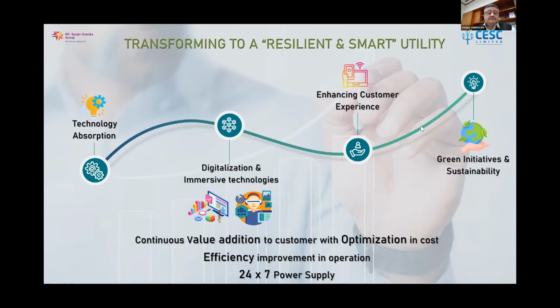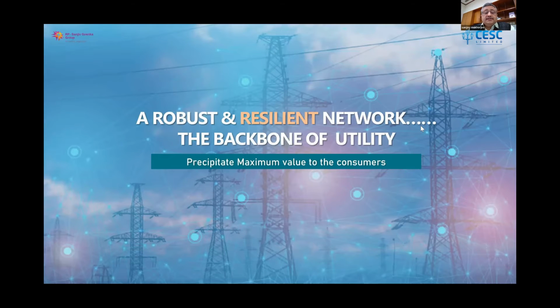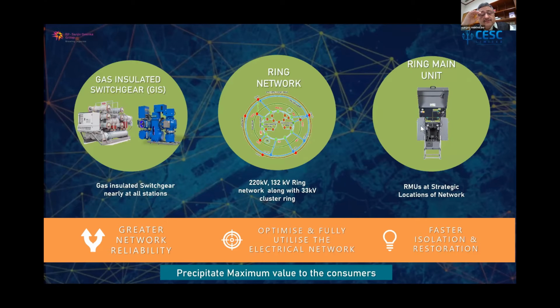Now, going ahead, if we talk about a robust and resilient network, which is the very backbone of any utility, we start from the 220 kV level, because we are one of the only discoms in the country having 220 kV as its distribution network. We have our own network starting from 220 kV going down to 220 volts. We have been using gas insulated switchgears since the mid-90s, and almost all stations use them now, shifting over time from outdoor switchyards to gas insulated switchgears.